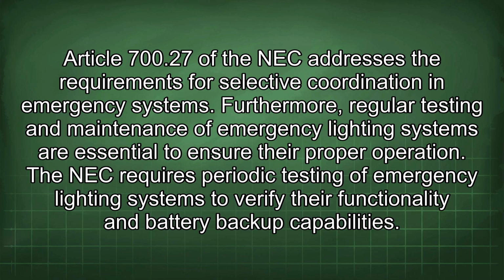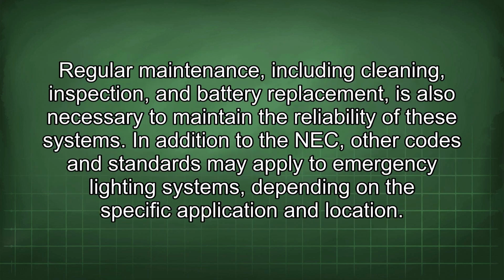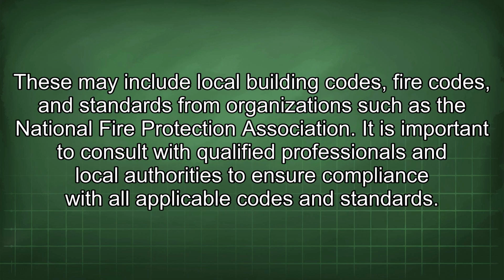Furthermore, regular testing and maintenance of emergency lighting systems are essential to ensure their proper operation. The NEC requires periodic testing of emergency lighting systems to verify their functionality and battery backup capabilities. Regular maintenance, including cleaning, inspection, and battery replacement, is also necessary to maintain the reliability of these systems. In addition to the NEC, other codes and standards may apply to emergency lighting systems, depending on the specific application and location. These may include local building codes, fire codes, and standards from organizations such as the National Fire Protection Association. It is important to consult with qualified professionals and local authorities to ensure compliance with all applicable codes and standards.